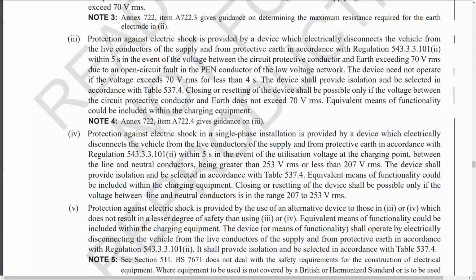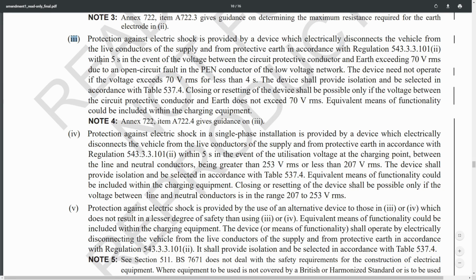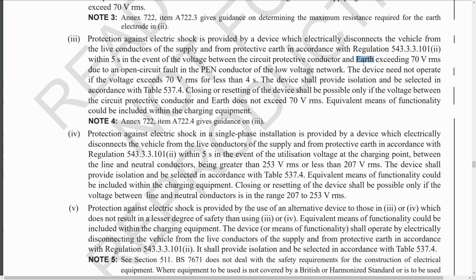Number 3 here, this is essentially the same as before. It's this mythical device which disconnects the various conductors within 5 seconds. If you get a voltage greater than 70 volts between the PEN conductor, which is essentially the earth terminal of your installation, and the actual earth outside, this would need a reference earth electrode installing, and then it would monitor the voltage between those two and disconnect all of the conductors, including the earth conductor or the protective conductor, if this situation occurs. This doesn't exist.